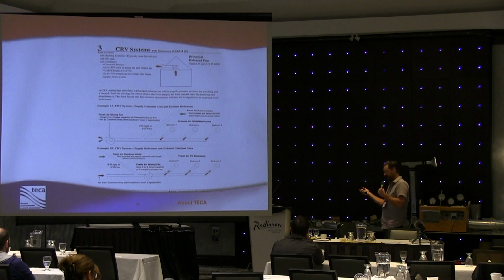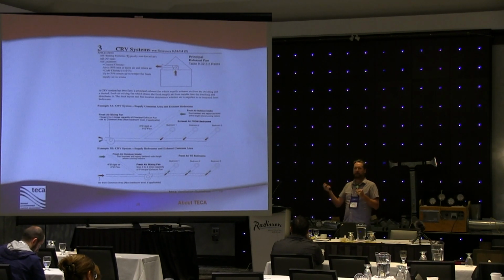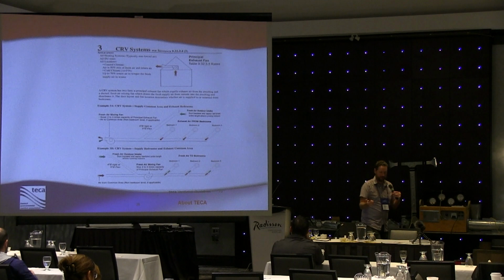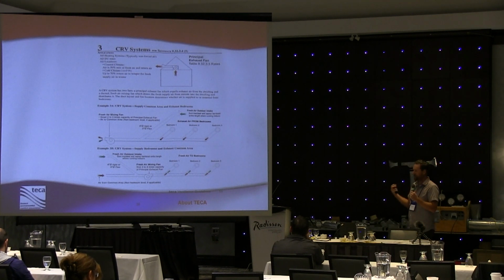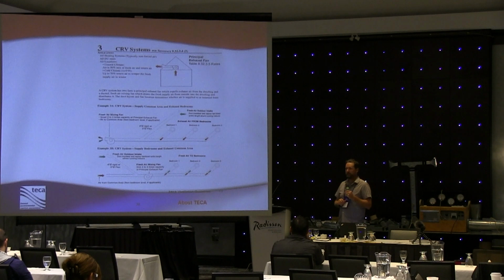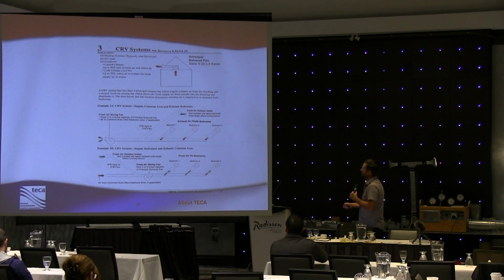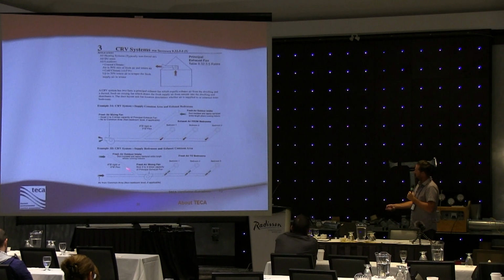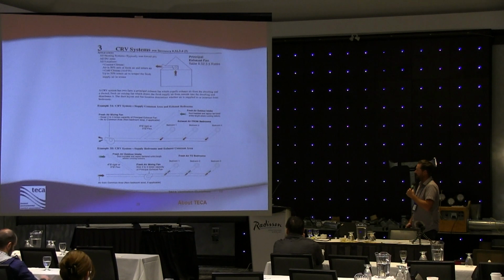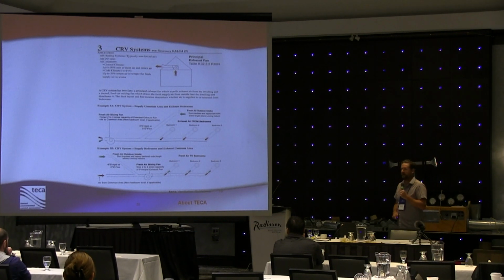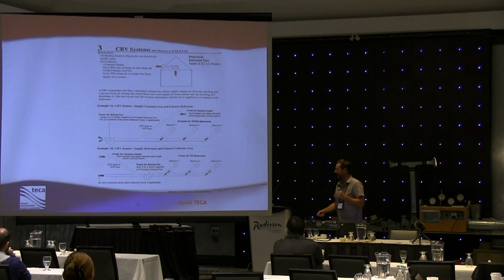You can imagine if we're drawing fresh air in directly from outside and piping that directly into bedrooms, that we're going to get some complaints. We're going to have some homeowners that aren't going to be very happy, especially in a cold climate when we've got below freezing air blowing into their bedroom. Not a good scenario. So what we do is we take a mixture of fresh air from outside and stale air from inside the building, and we blend those two in what we call a fresh air mixing fan. That fresh air mixing fan is going to deliver that mixture of air to the bedrooms, and we're going to get our fresh air delivery in that way.